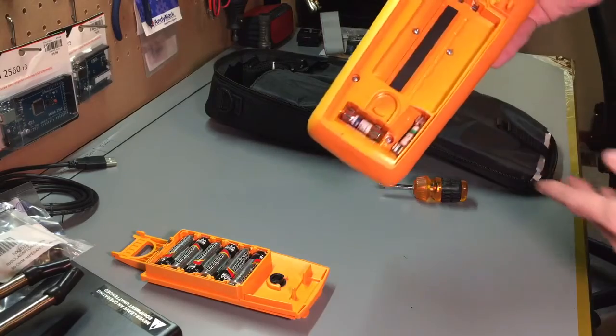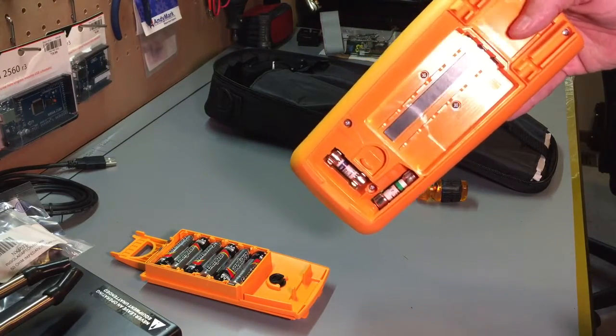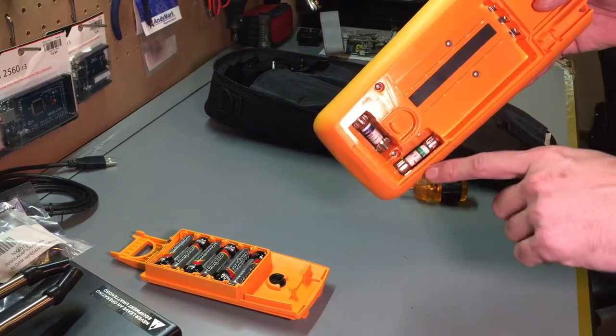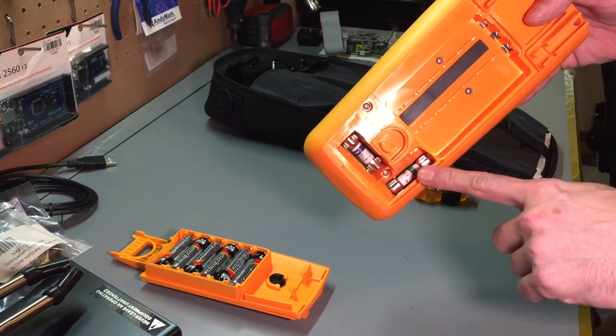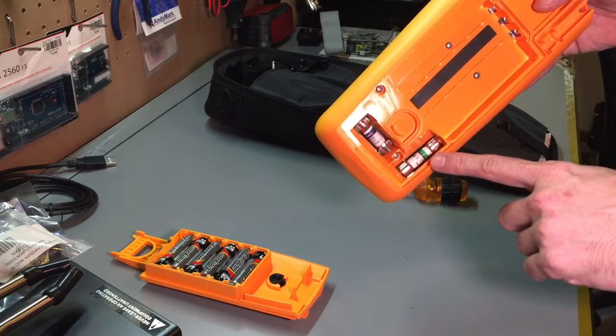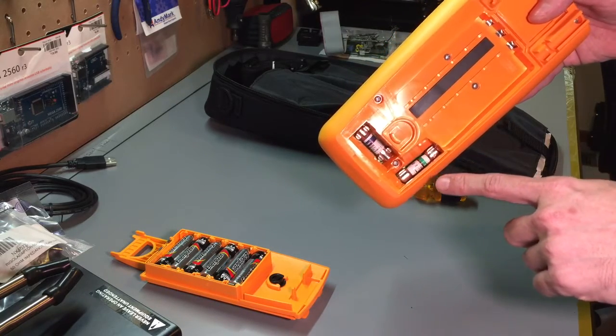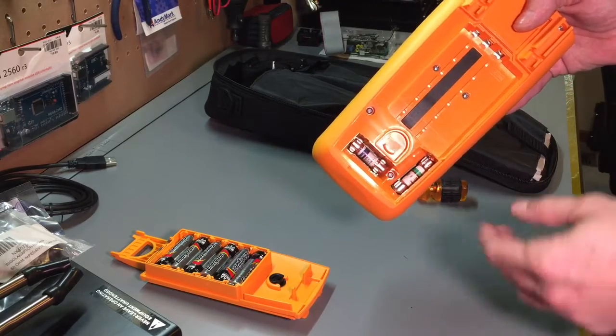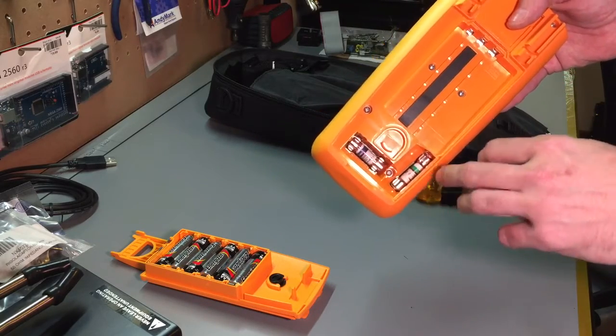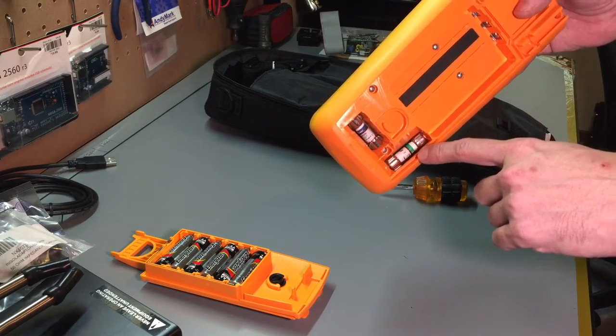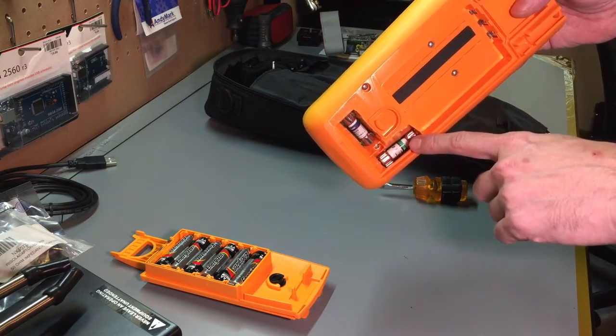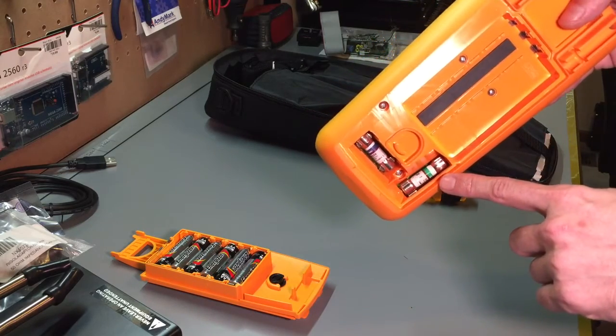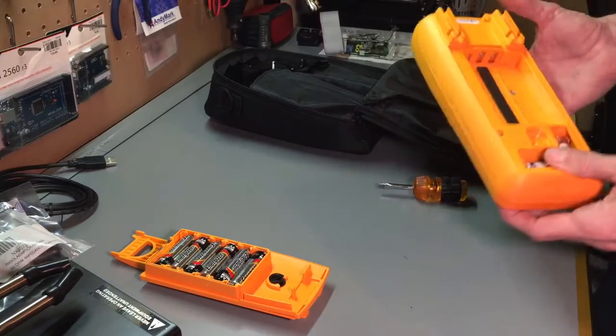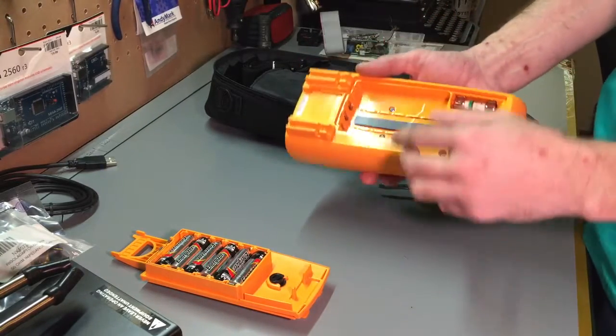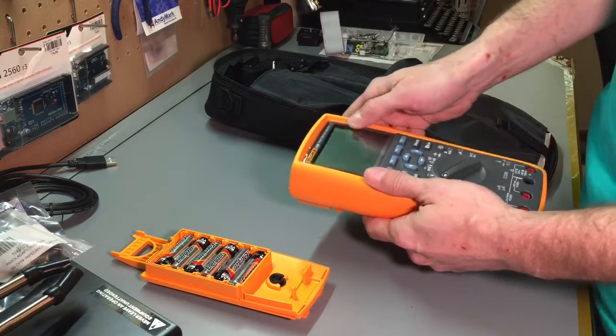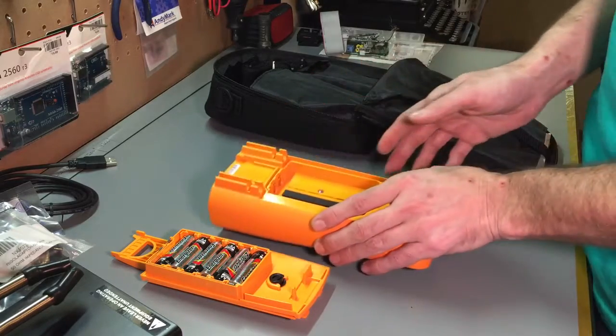If you're not certain of the low amperage you're looking to monitor, there's a good chance you'll blow that 400 milliamp fuse often, and they're not cheap. So if you think you may do that, use another meter first if you have anything that will measure low current like that. I was told you can get about 5 of these fuses for about $30 from some suppliers on eBay. I may have to do that. It's a good idea to have a spare of both fuses on hand in case you accidentally trip it and pop one.